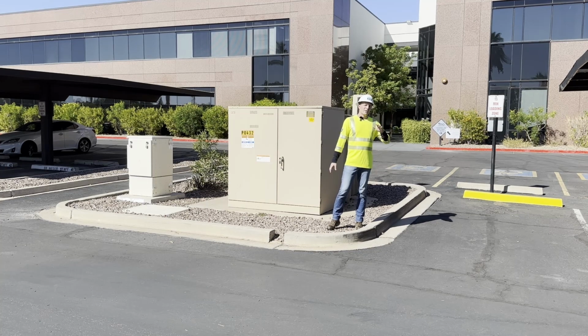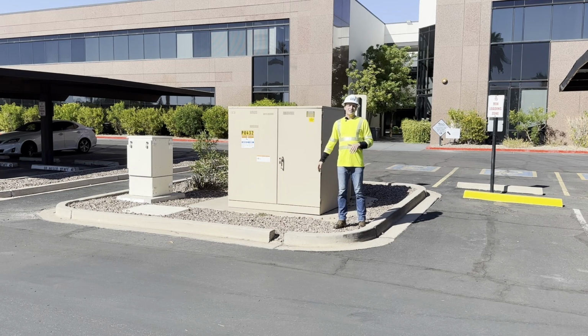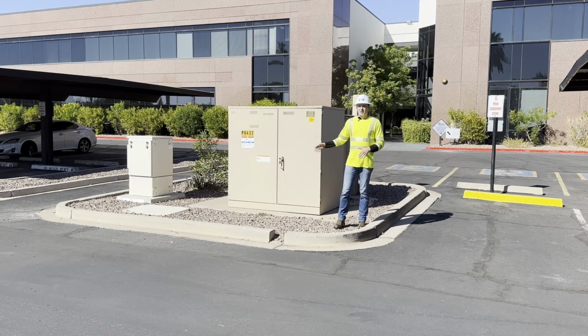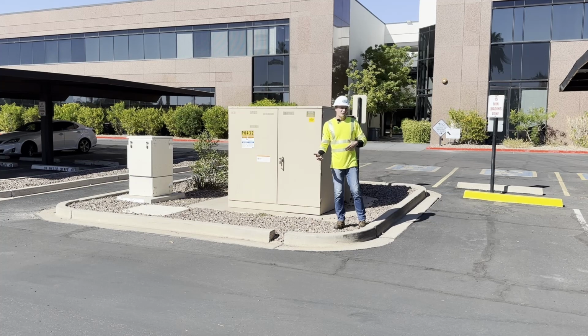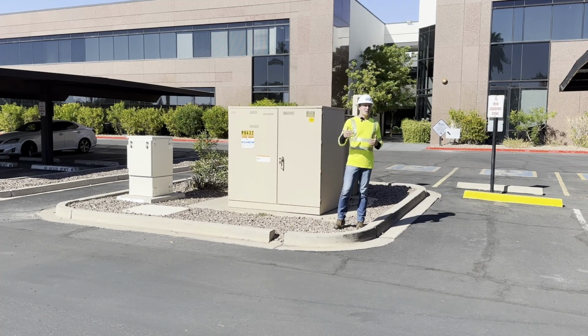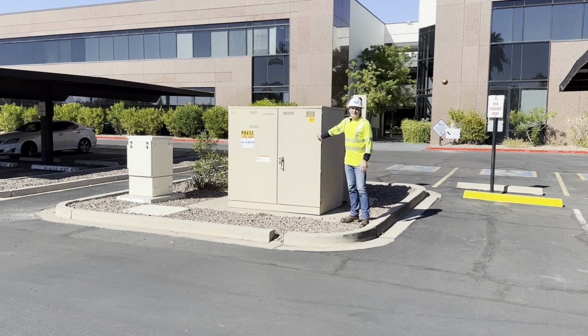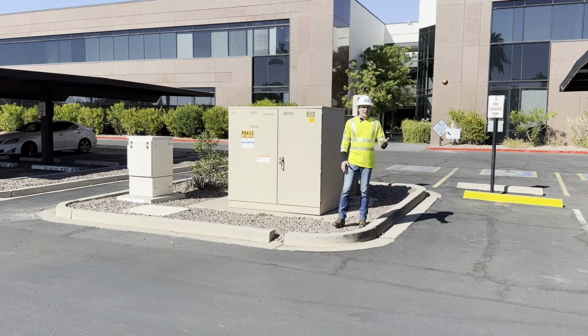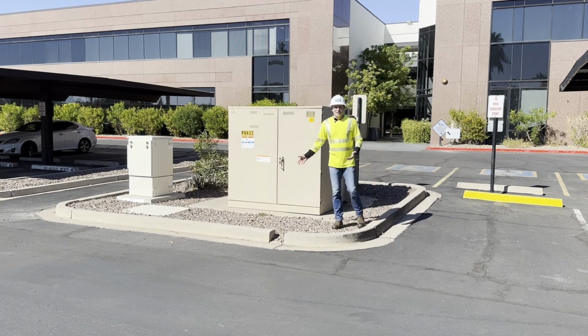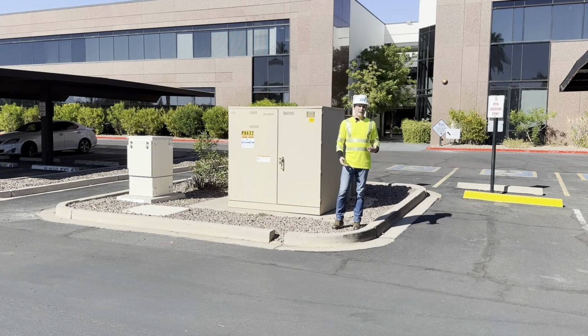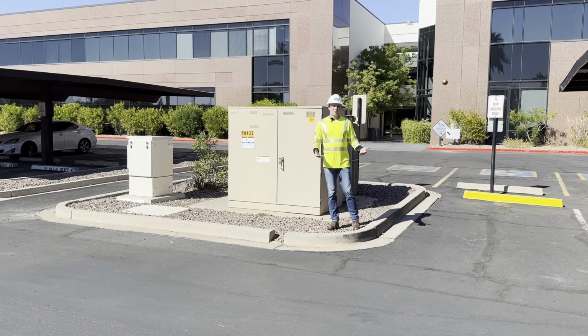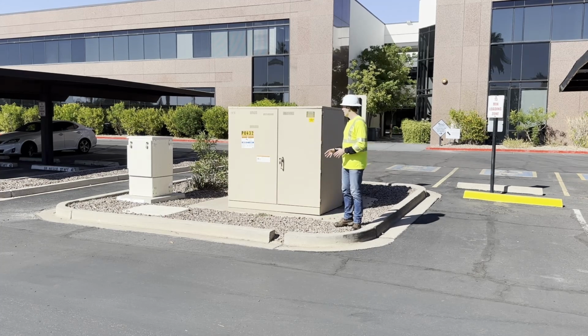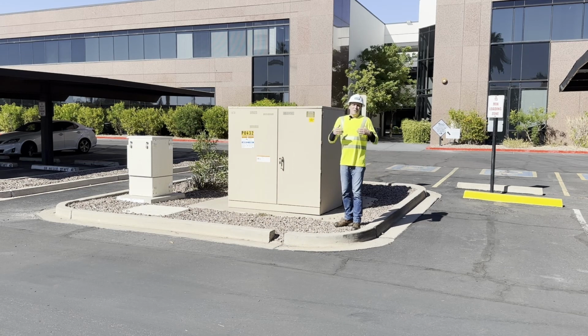It's not what we have to do on the customer side with the National Electric Code. They can kind of do what they want when sizing these transformers, and depending on what they do, it can create limitations sometimes. If they undersize your transformer, there's only a certain amount of peak load that you can reasonably hit, because you can't just run these things at 150% of their rated capacity for too long, because they'll burn out, they'll break down. Even though there's no moving parts, it is still a piece of equipment and it can fail over time. So it's really important to work with your utility when you're doing your DC fast charging project or other projects in the EV space, to make sure that these transformers are sized properly for the current and future load of your projects.